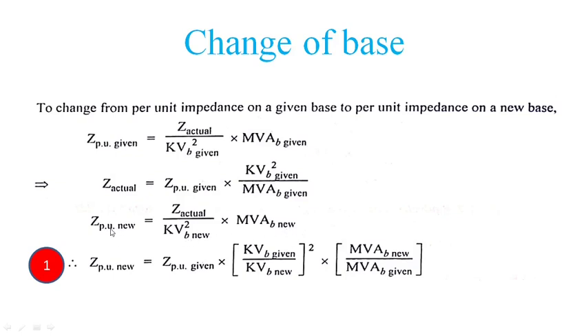So we want to get the expression for Z per unit new in terms of Z per unit given. You can substitute the expression for Z actual from the previous one. Substitute this Z actual in this equation and you will get Z per unit new is equal to Z per unit given into, so segregate the kVB and MVA ratios, for easy remembering, Z per unit given into kVB ratios squared into MVA ratios.